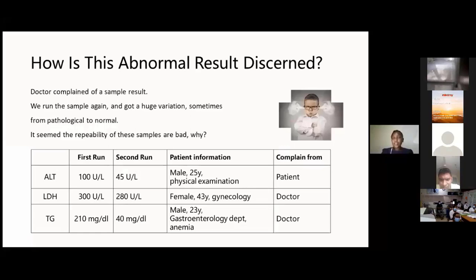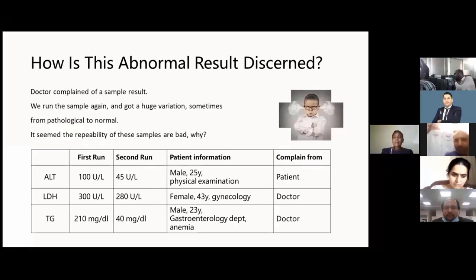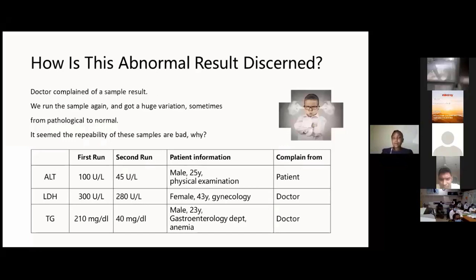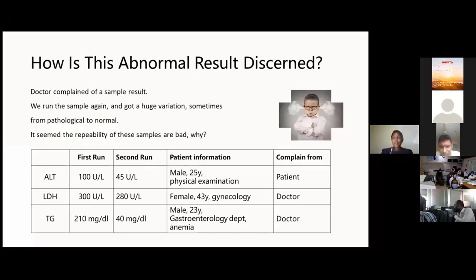After confirming that it was the correct sample, we would rerun the samples and the results would have huge variations, sometimes from pathological to normal. It seemed that the repeatability was bad. You'd find an ALT on a first run giving a result of 100, then on the second run 45 units per liter. And it's the same sample, same timing, same personnel, same everything. You'd find an LDH on a first run giving 300 units per liter, and then on the second run 280 units per liter. Such a huge discrepancy.